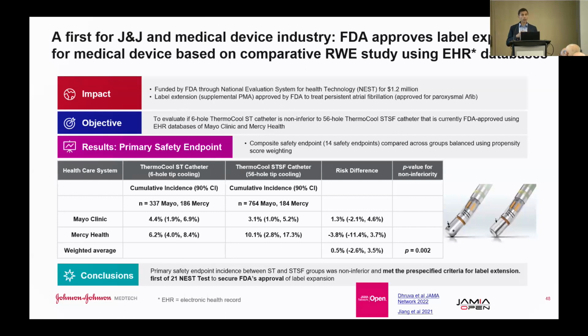That allows better cooling of the tip, which is important for preventing charring of tissue, which, if it gets overheated, can cause stroke. And also because you're burning inside the heart, it allows the clinician to not worry too much about overheating, so they can make sure that they get a good ablation that really cuts off the signal that's causing the arrhythmia. And atrial fibrillation has about a 5-fold risk factor for stroke, so it's important to treat.